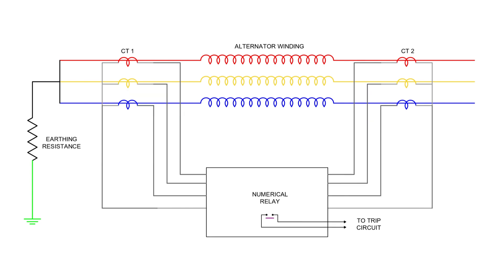Although the example we've just discussed uses electromagnetic relays, in modern power systems, we typically use numerical relays for protection. In these systems, the secondary outputs from the current transformers, CT1 and CT2, are fed directly into the relay. This relay continuously monitors the incoming current values from both ends of the alternator winding.